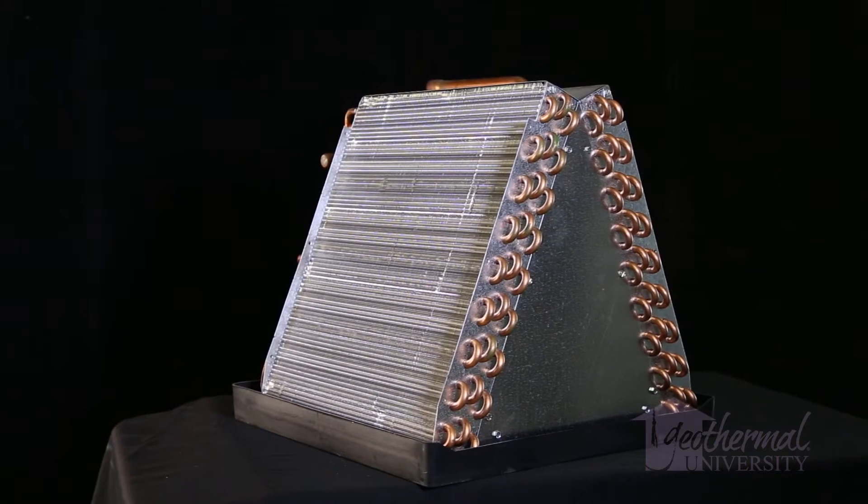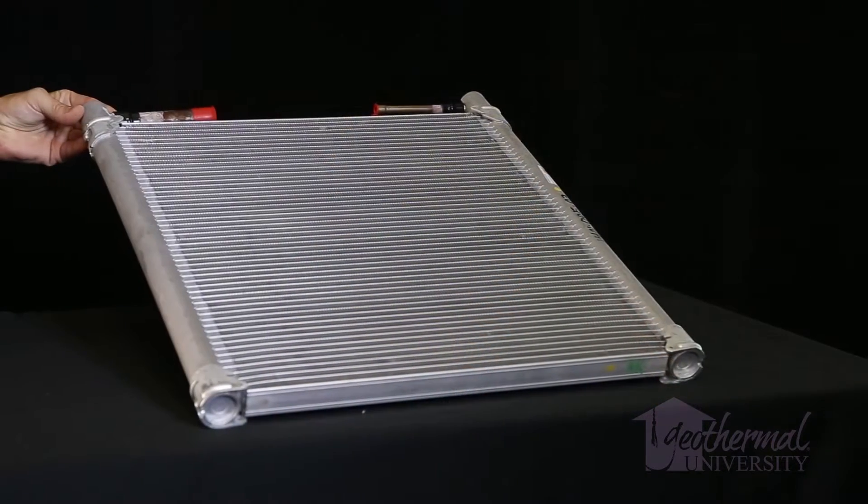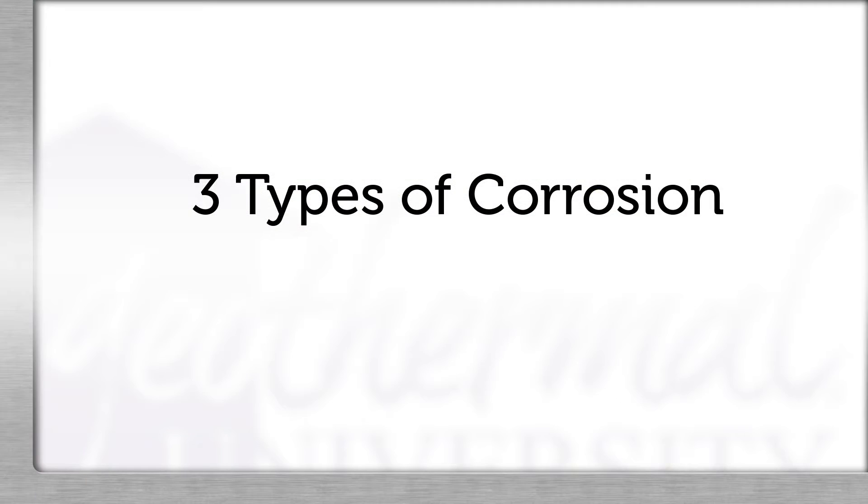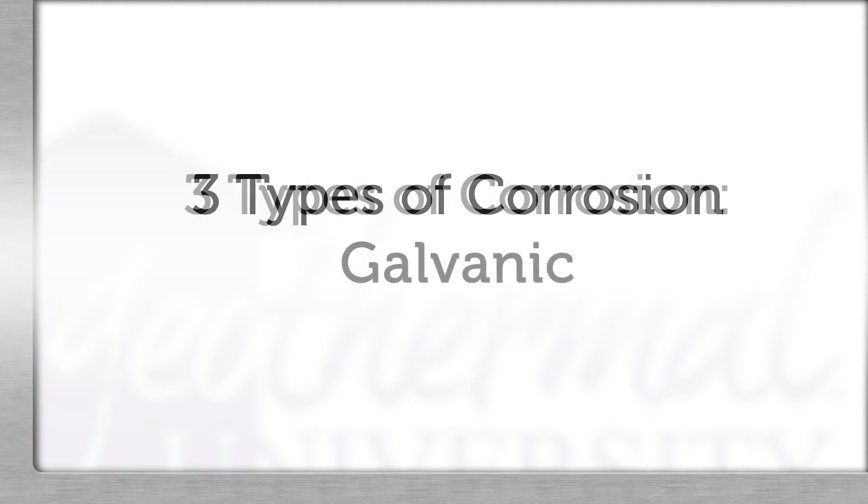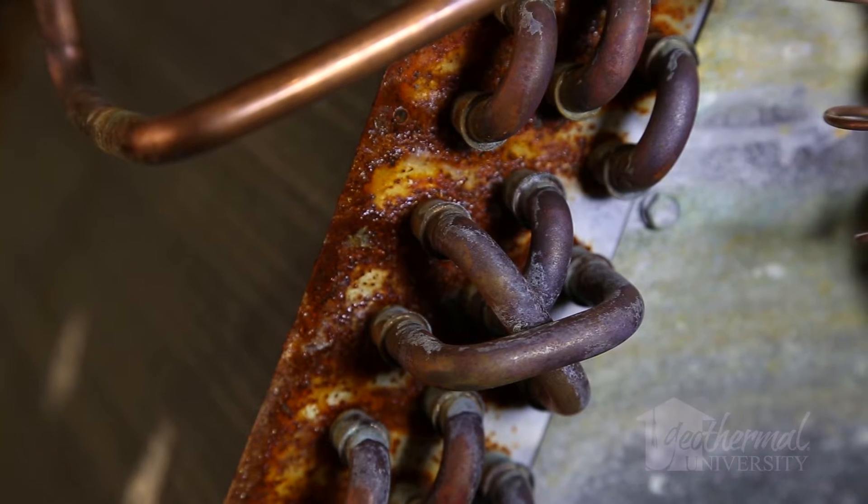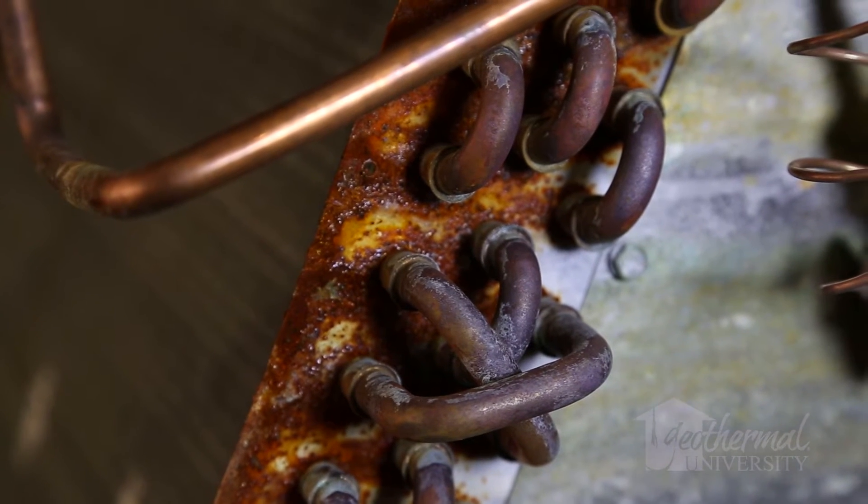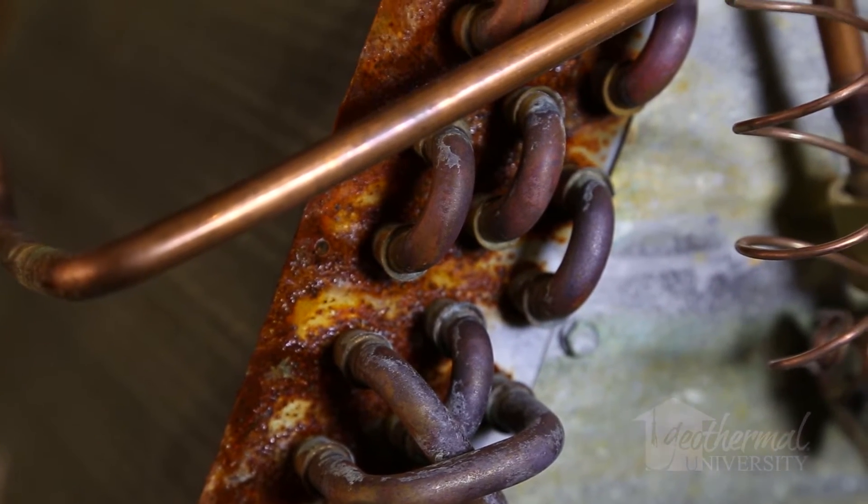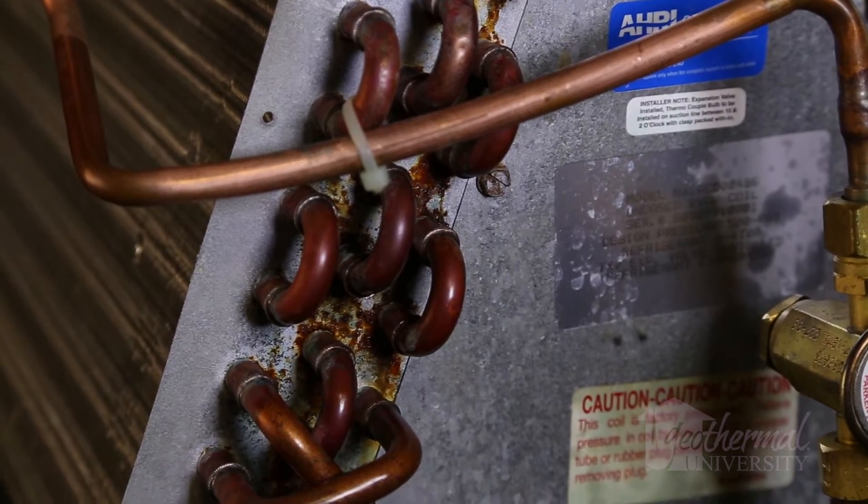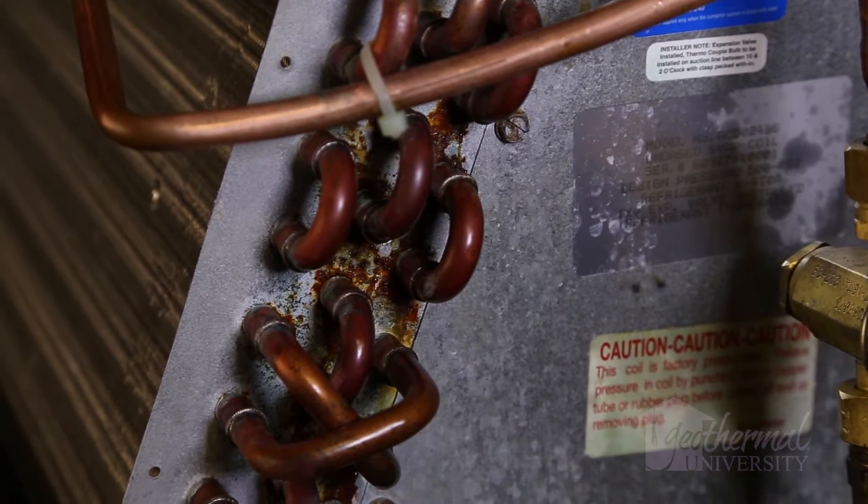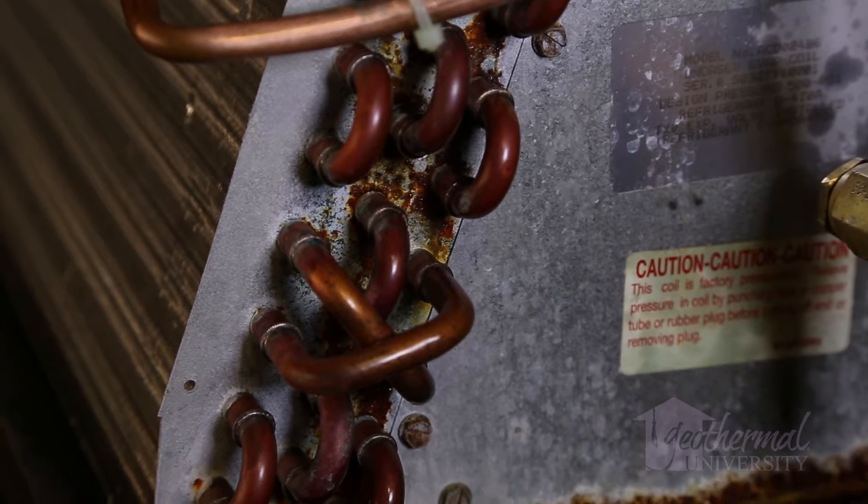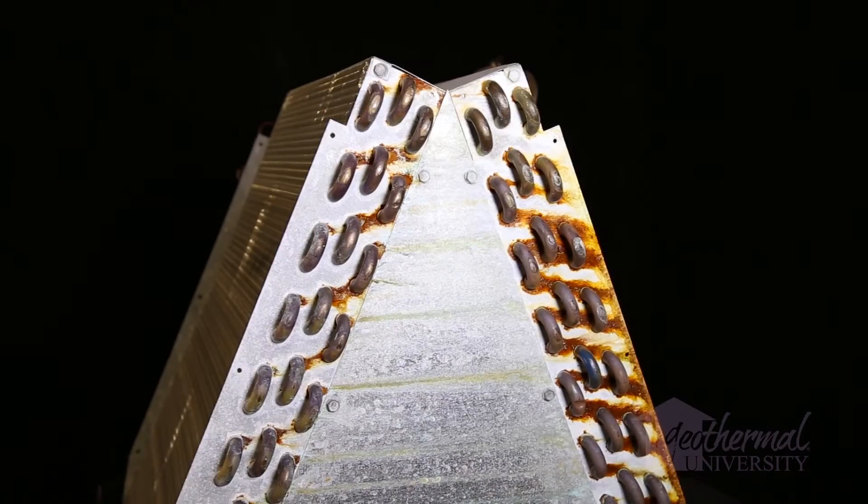Before we begin we'd like to discuss the corrosion that an air coil is subject to when installed in HVAC equipment. We'll briefly define the three kinds of corrosion present. Galvanic corrosion is an electrochemical process in which one metal corrodes preferentially to another when both metals are in electrical contact. Crevice corrosion refers to corrosion that naturally occurs in tight mechanical bonded junctions such as where aluminum fins are pressed into copper tubes. The spaces between the dissimilar metals are referred to as crevices.